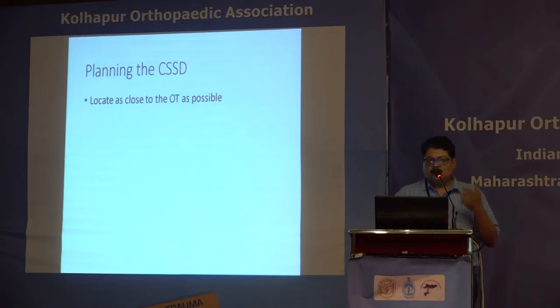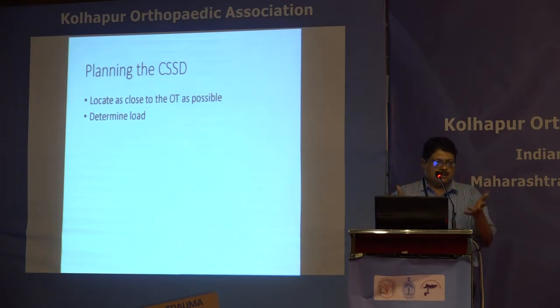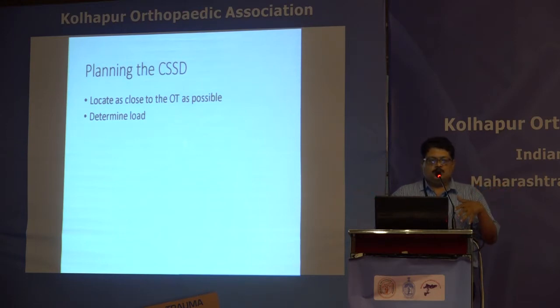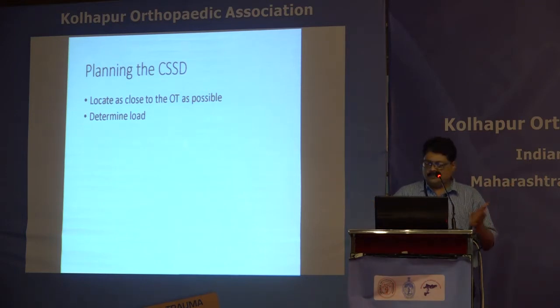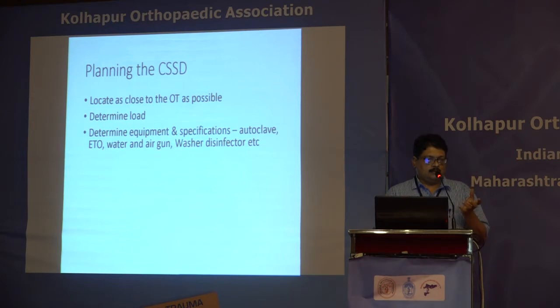When planning the CSSD, locate it as close to the OT as possible — clean areas close to the OT, dirty areas as far away as possible. Determine the sterilization load, which depends on the surgeries done each day and how many trays and drums are required per surgery. This varies between surgeons: some use just one or two trays, others may open four or five trays.